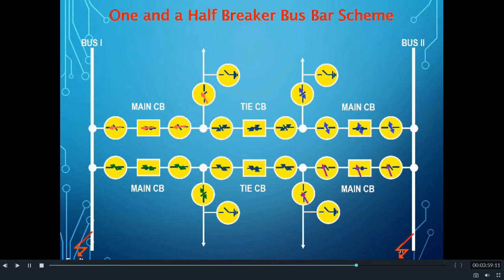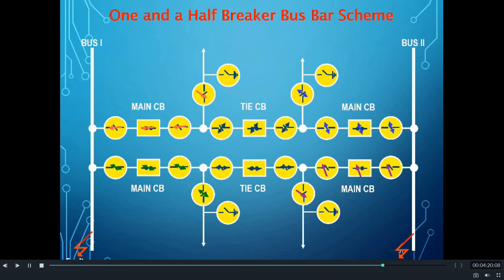With faults on both bus one and bus two simultaneously, the feeders are still working normally as they are interconnected to each other — operating without any bus. The only limitation is that the feeders get interconnected and act as a separate network. In such busbar schemes, faults in any circuit breaker or both buses together will not create any interruption in the system.